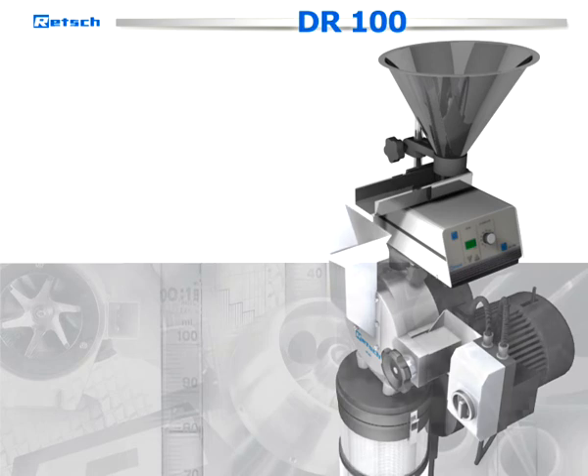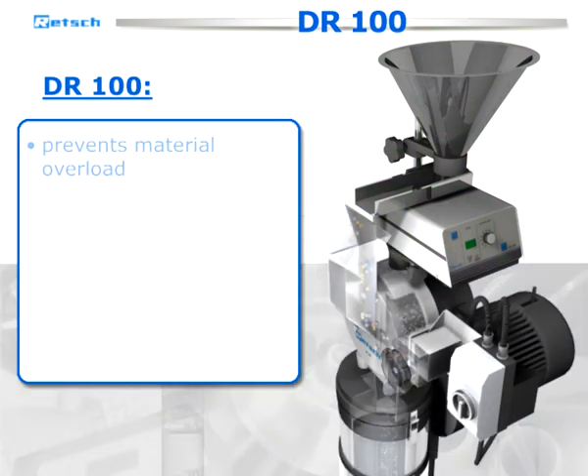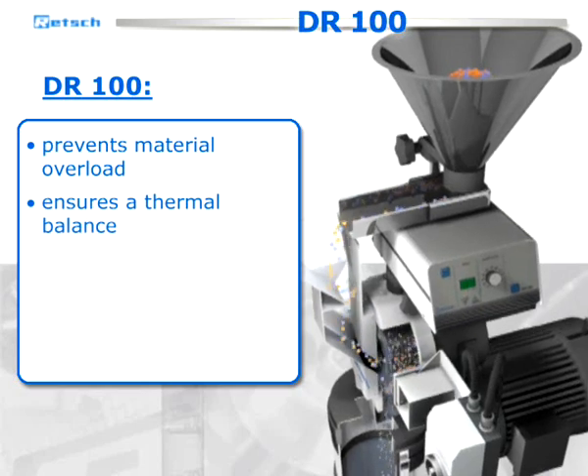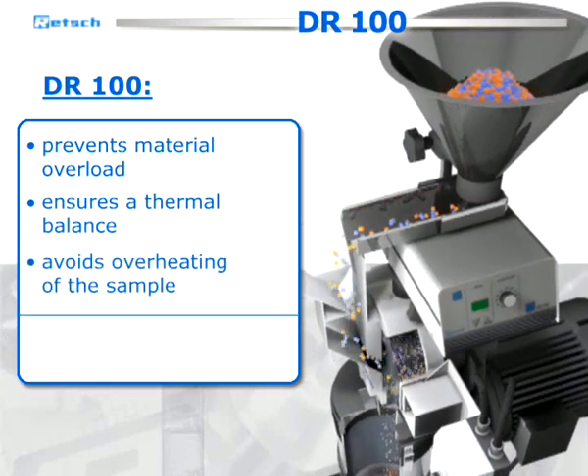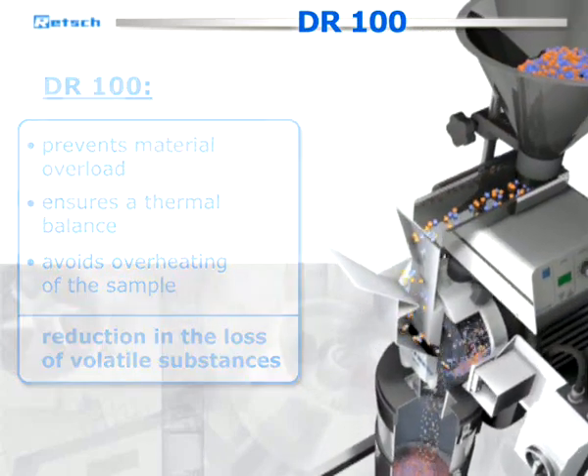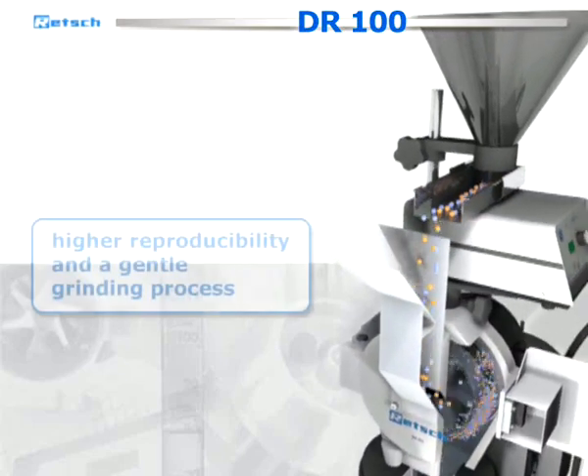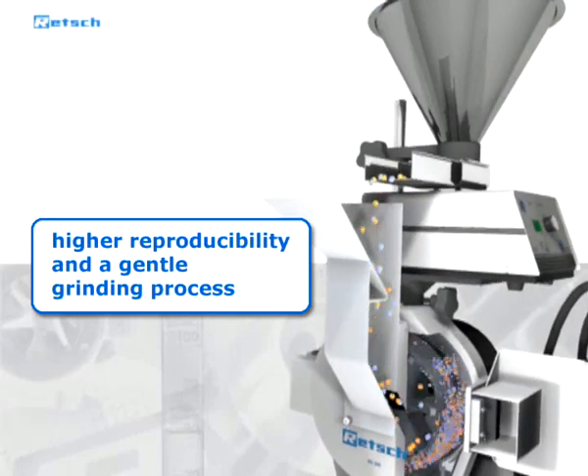If larger amounts are to be processed, RETSCH offers the sample feeder DR100. It prevents material overload, ensures a thermal balance during the entire comminution, and avoids overheating of the sample. This leads to a significant reduction in the loss of volatile substances. Therefore, as a result of less material stress, the DR100 allows a higher reproducibility and a gentle grinding process.